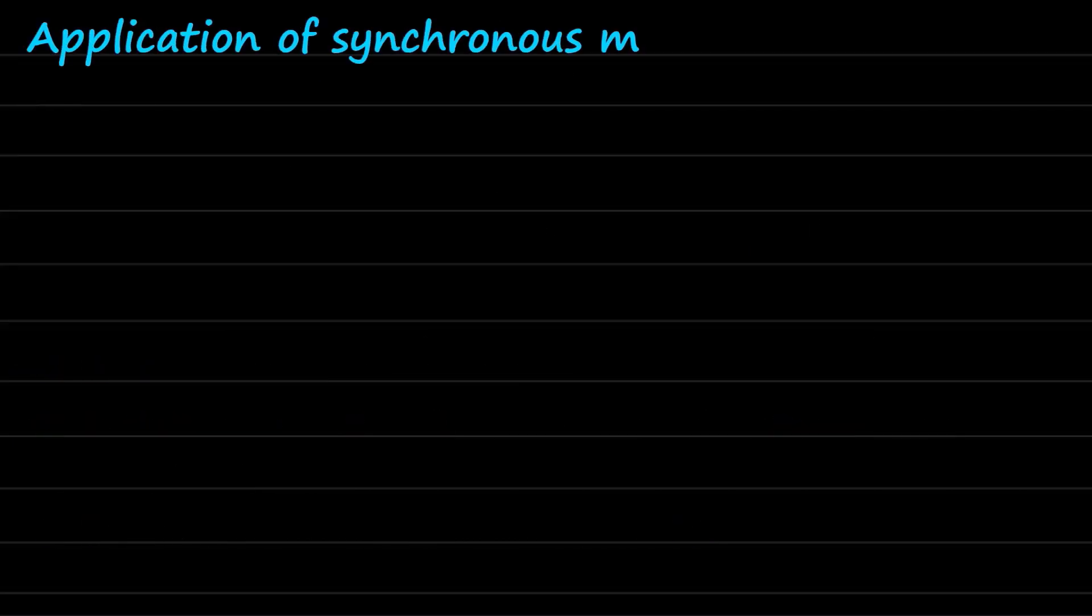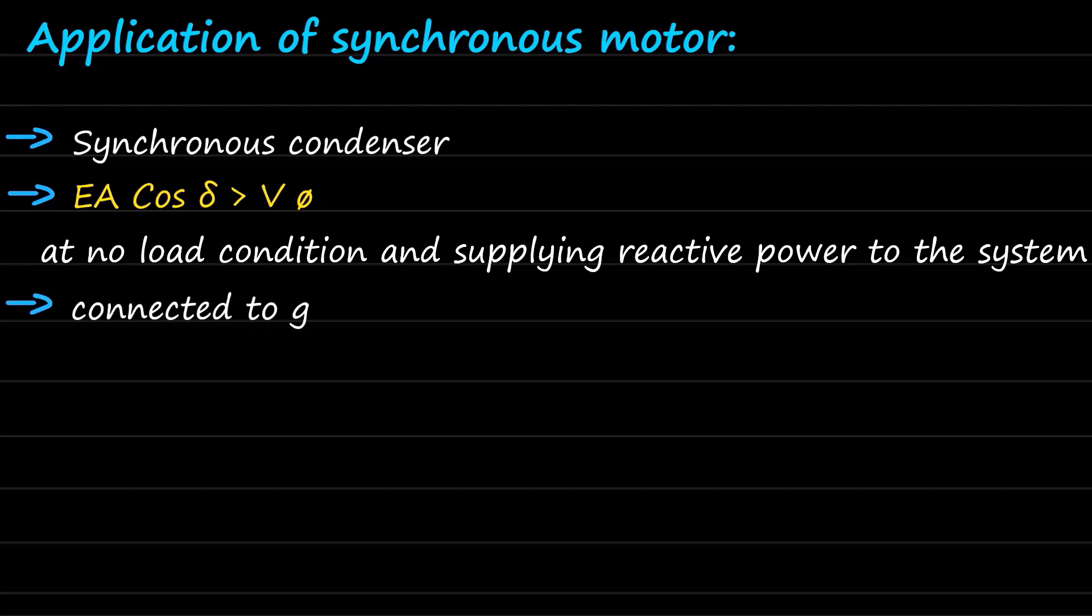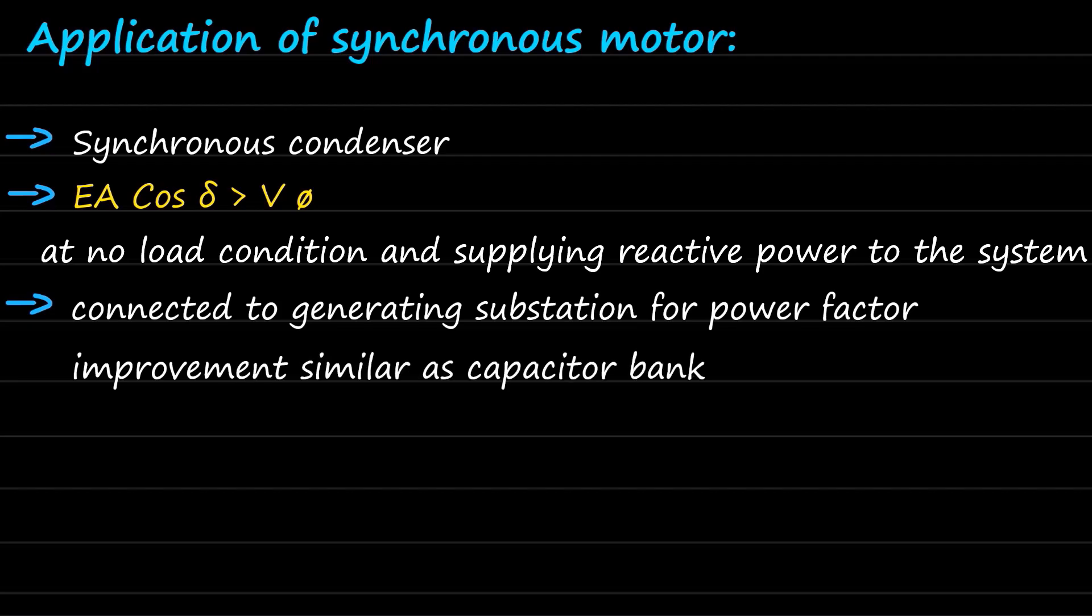Application of synchronous motor. Let's talk about an application of synchronous motor, that is, synchronous condenser. When synchronous motor is operated in an overexcited mode, that is, Ea cos delta is greater than V phi at no load condition, and supplying reactive power to the system, then such a motor is also known as synchronous condenser. They are connected to generating substations for power factor improvement, similar to capacitor banks.